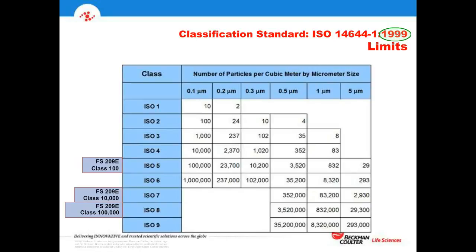In the standard, there are 9 different classes of rooms, ISO 1 through ISO 9, going from very clean at ISO 1 to not very clean at all in ISO 9. Most operations tend to be in the range from 5 to 8. But not always. Depends on the particular type of industry and method. Certainly, semiconductor industry utilizes ISO 2 and even ISO 1 at times.